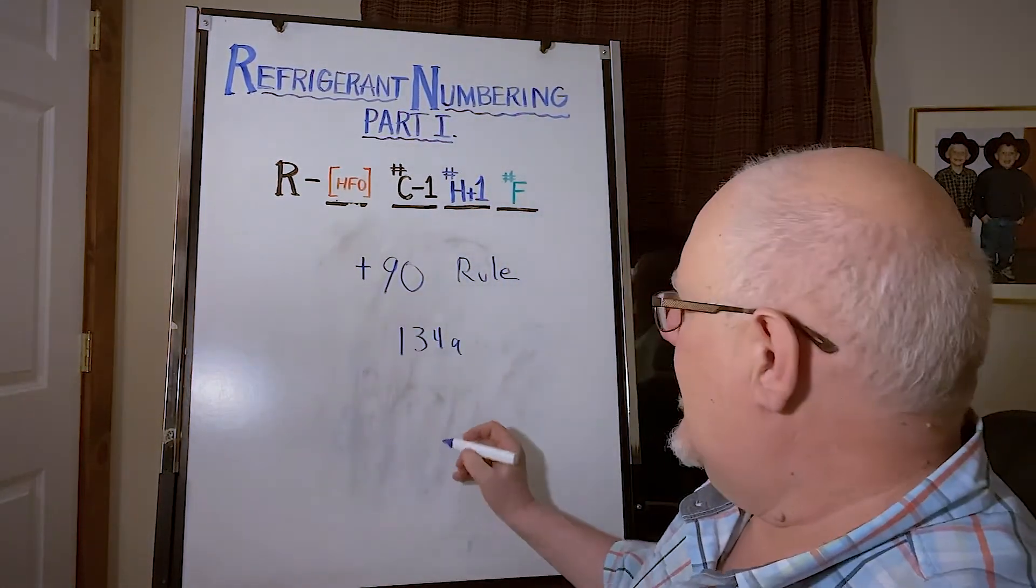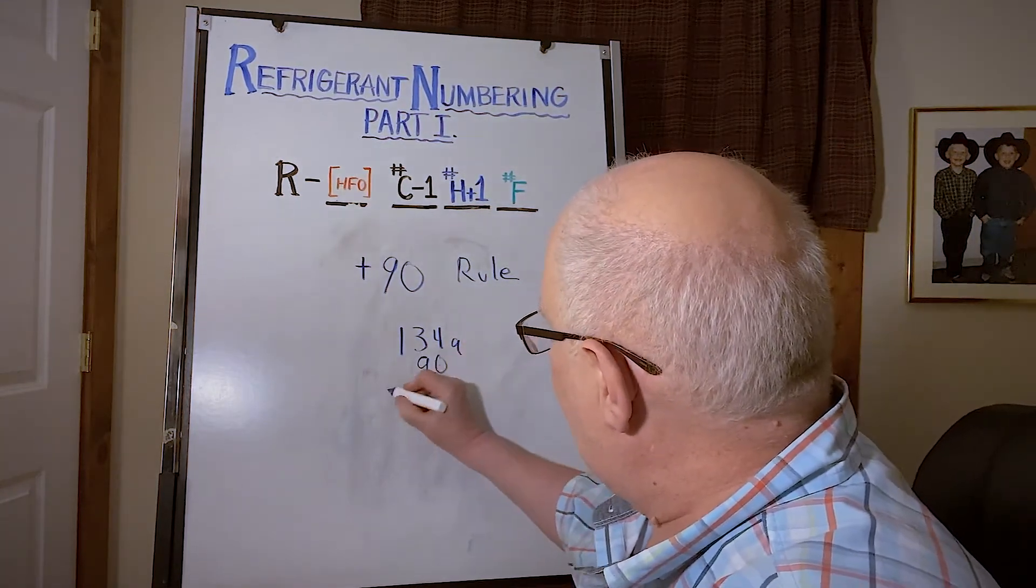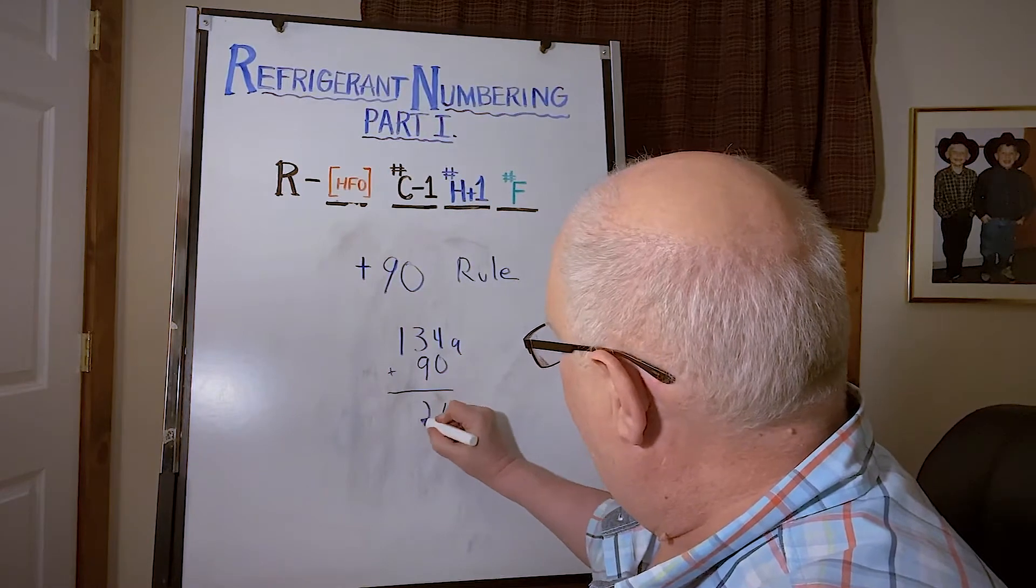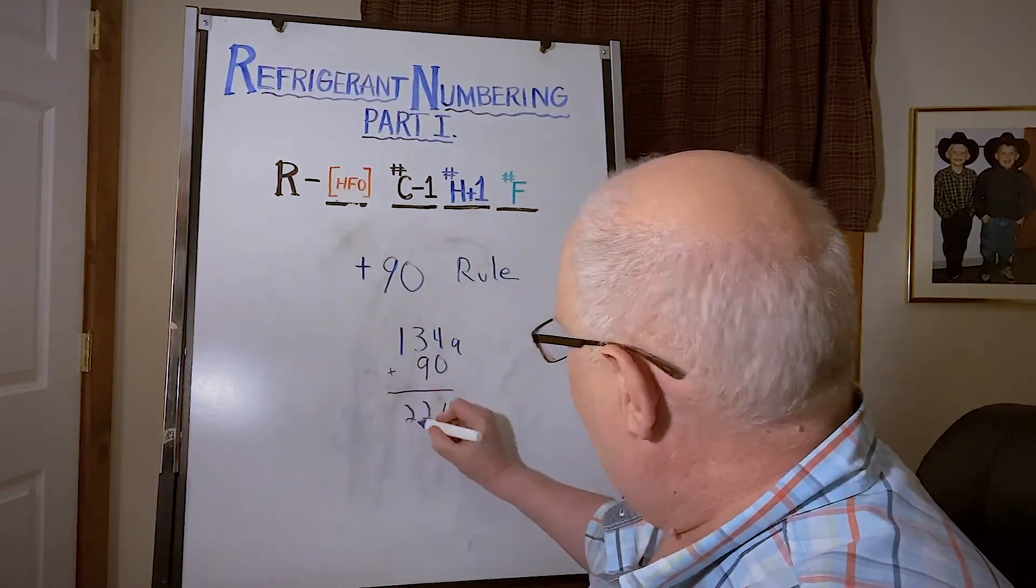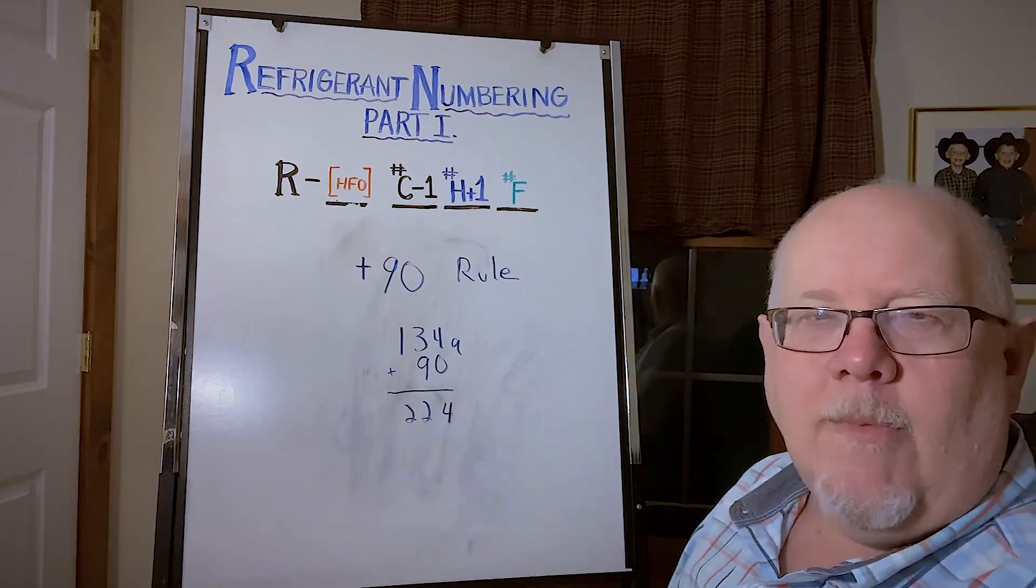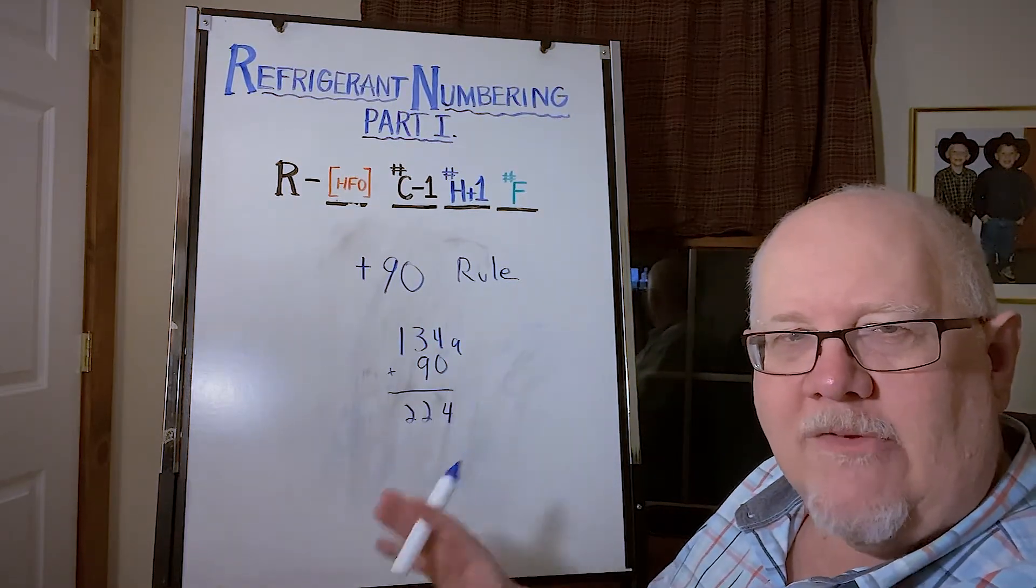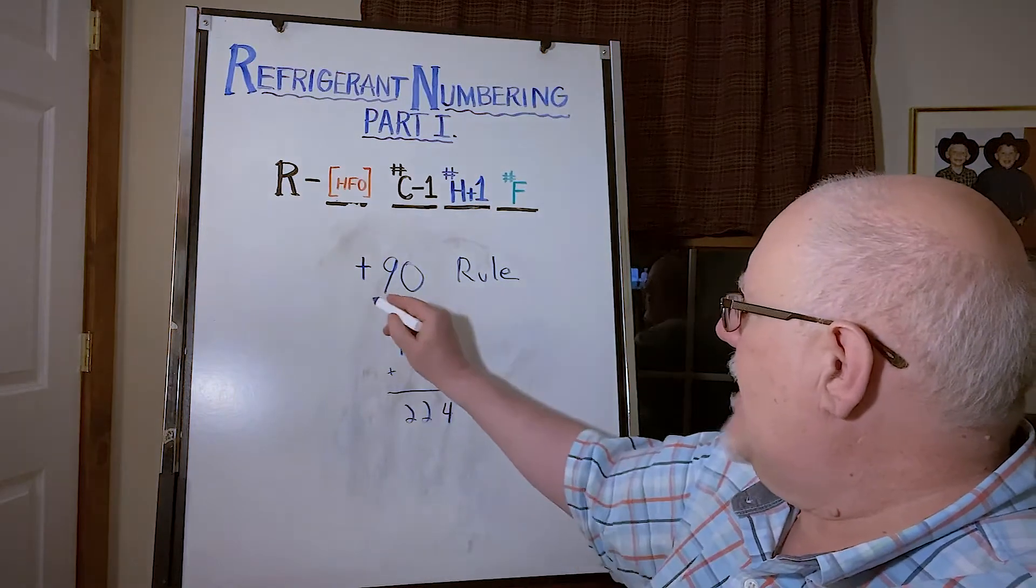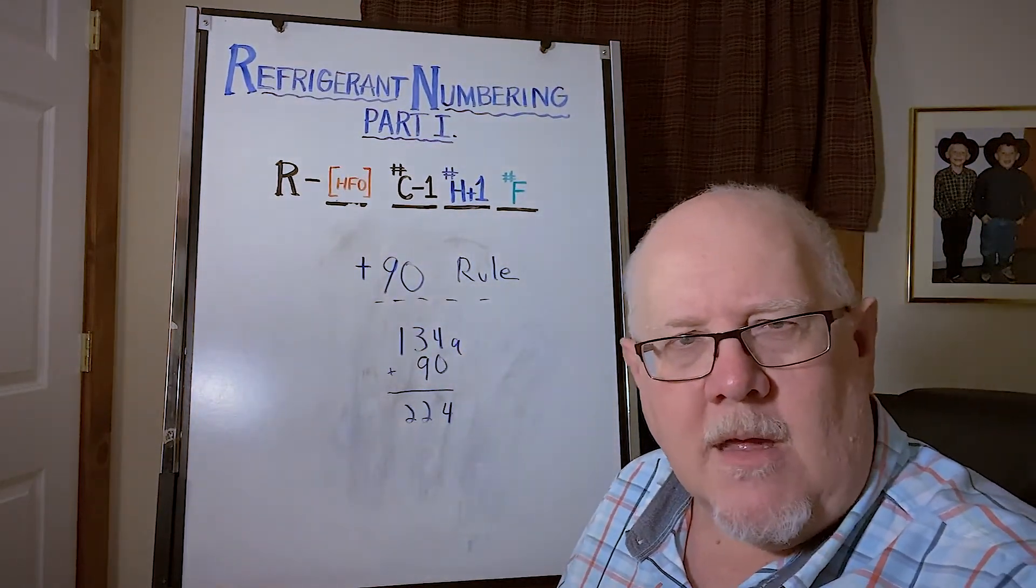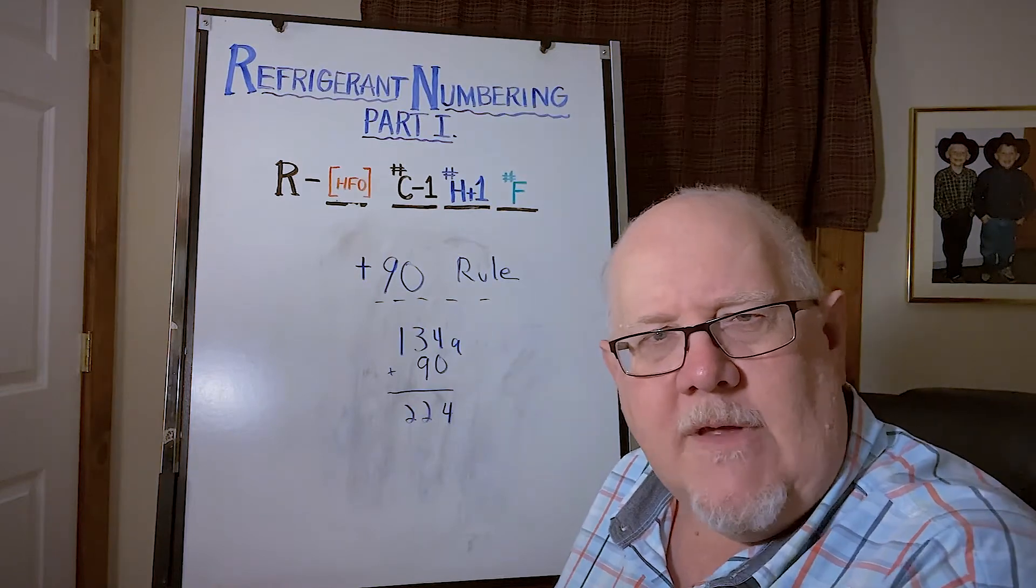So again, 134a, if we followed this and added 90 to it, this will give us directly now four fluorines, two hydrogens, two carbons. Don't have to worry about whether it's plus one minus one. Some people like to use the plus 90 rule, some people think it's obvious without it, but I offer that to you if it helps you remember it.